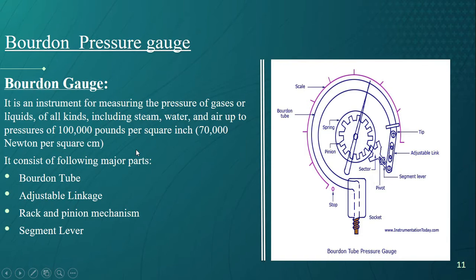Bourdon tubes are known for their very high range of differential pressure measurement. The Bourdon pressure gauges used today have a slight elliptical cross section, and the tube is generally bent into a C-shape with arc length of about 270 degrees. The detailed diagram of the Bourdon tube is shown in the figure. The basic idea behind the device is that cross-sectional tubing when deformed will tend to regain its circular form under the action of pressure.